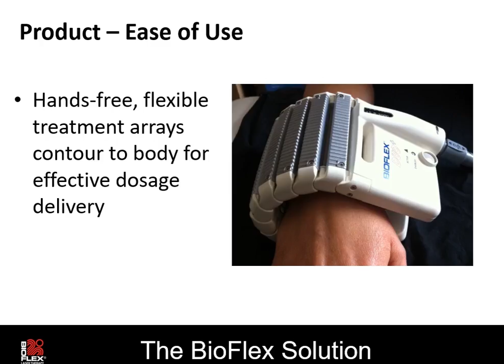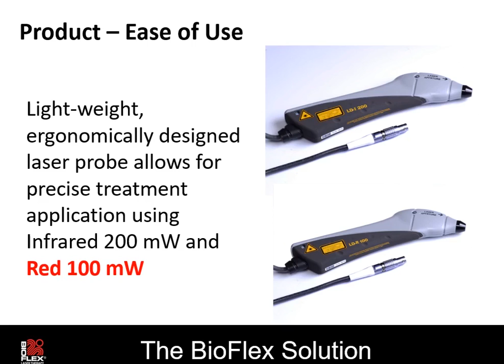The laser probes, as I mentioned earlier, vary from an output of 200 milliwatts to 100 milliwatts, depending if it's infrared or red. And they're designed to be held on the skin for a much shorter period of time, usually anywhere from a few seconds to as many as 15 to 20 seconds before moving to the next point. And again, I'll explain the reasoning for this and why you would be holding it for longer or shorter periods of time as we move along in the training webinars.